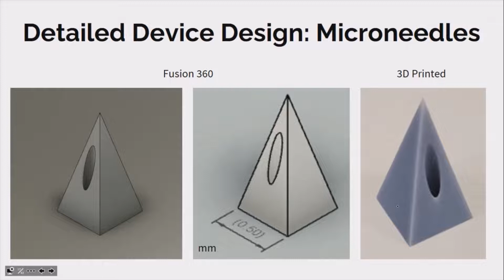The material we chose for the microneedles was silicon. This was due to its high Young's modulus, its non-ductile nature, and its injection hardness, or implementation hardness, which made it an optimal material candidate for microneedle fabrication. The shape of the microneedles was chosen to maximize structural integrity, and the location of the opening was also offset from the center to make application better by keeping the pointed tip intact. It also helps reduce clogging upon application, and helps in ensuring the structural integrity of the device.